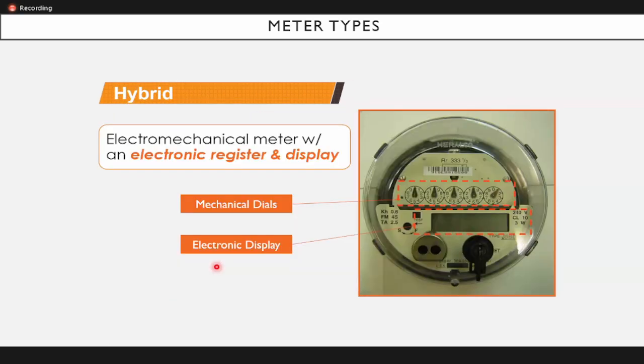In 1979, the first microprocessor-based electronic register was introduced as an additional component to an electromechanical meter. This combination was referred to as a hybrid meter. Compared with mechanical registers, electronic registers were more reliable when performing complex functions such as demand and could be provided at lower cost. In addition, electronic registers provided features not feasible with mechanical registers, such as time-of-use measurements, sliding demand intervals, switchable registers, tamper detectors, and self-tests.